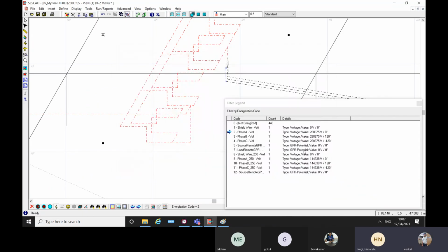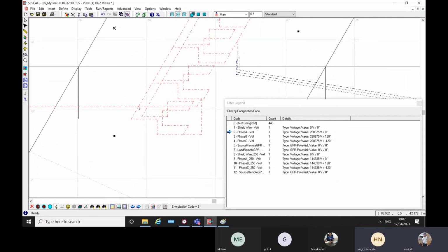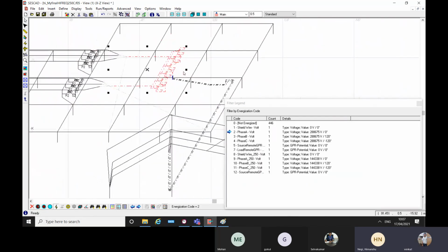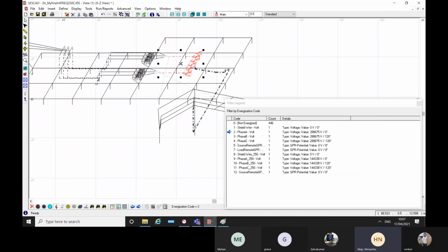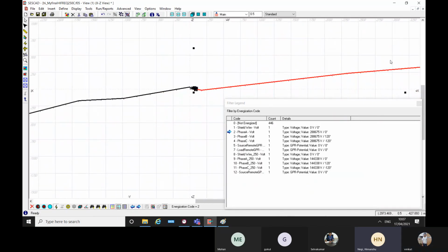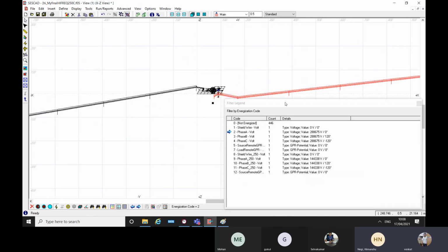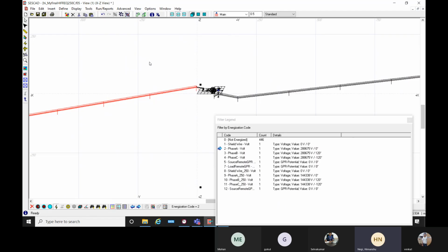That's what I explained. This is for the power frequency fault, by the way, not for transient, but what I'm showing is how you model a GIS in CDEGS. You really need a 3D drawing, showing how it comes here, goes, and all the discontinuities. Then after that it goes here to a local load, and then towards another substation. Nobody does this much detail modeling of the transmission line and everything. It is only someone who is an SES employee or who knows the software at a very advanced level.